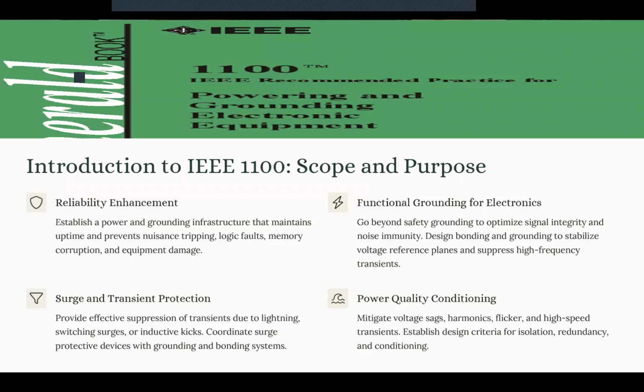Now, as we said, the IEEE 1100 is a recommended practice, it is not a mandatory standard, and it provides engineering guidelines for the powering and grounding of sensitive electronic equipment, which we call SPE. This standard aims to prevent failures, data corruption, or operational disruptions in the environment where even a minor electrical disturbance can cause significant damage or downtime. Now, let's talk about why this standard exists.